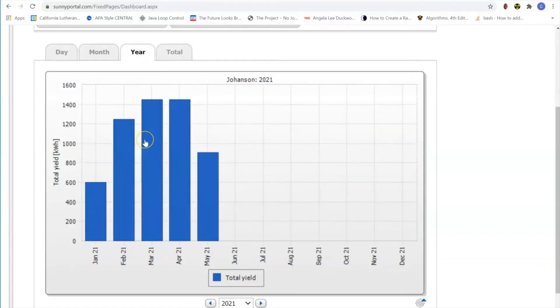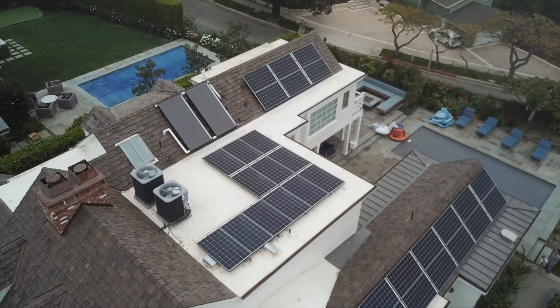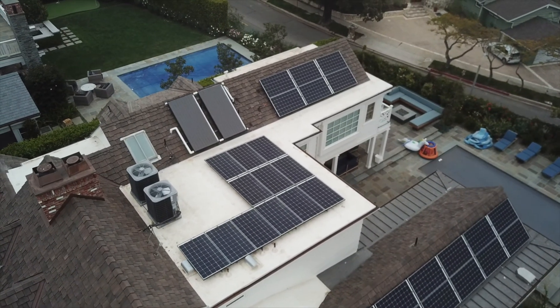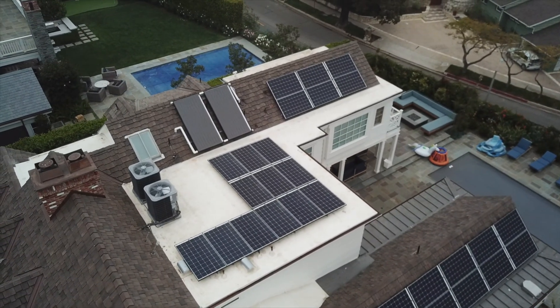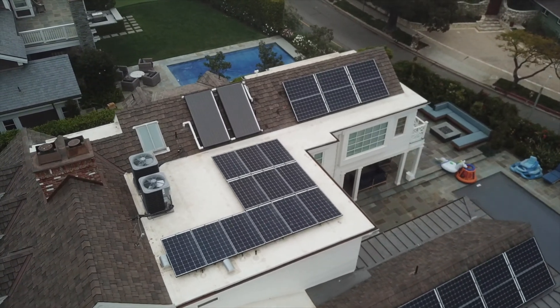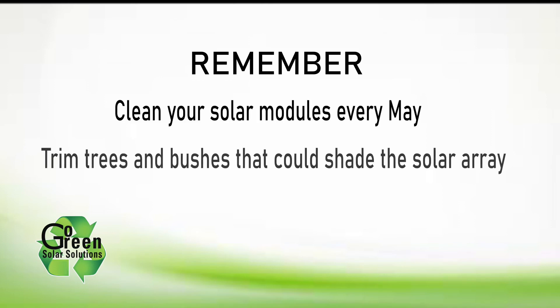You can see daily, monthly, yearly, or total power production. By looking closely at these numbers, we can tell if there is shading or dirt buildup on the solar modules that could compromise the performance of the system. Remember to clean your solar modules every May and trim foliage such as trees and bushes that could shade your solar array.